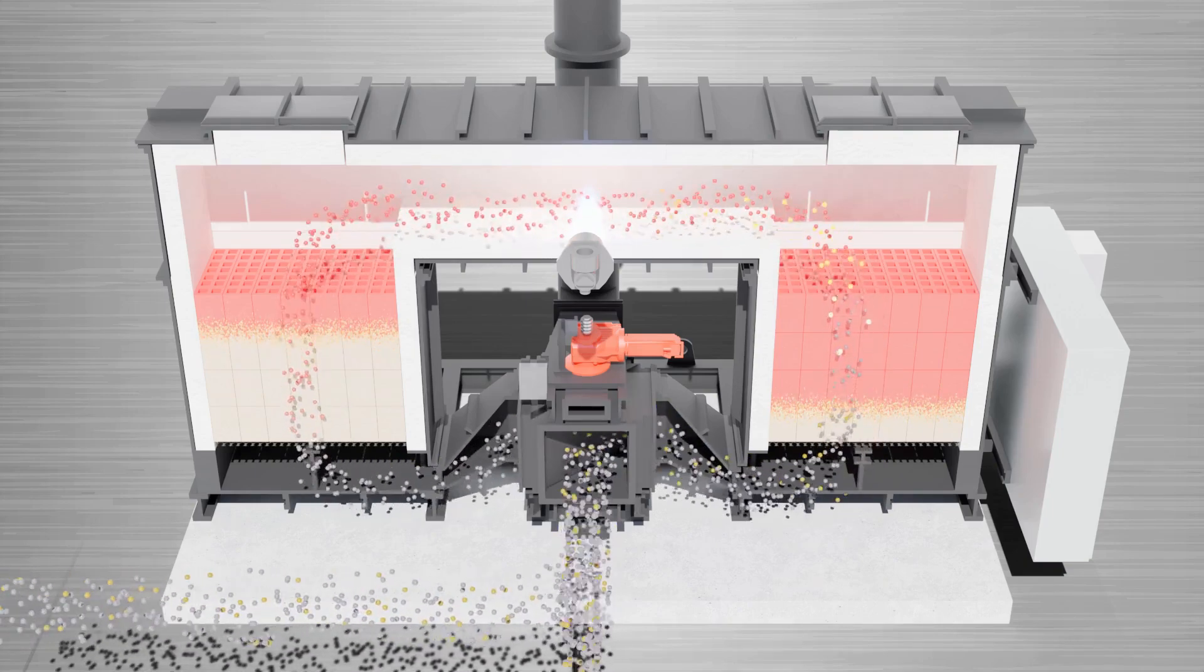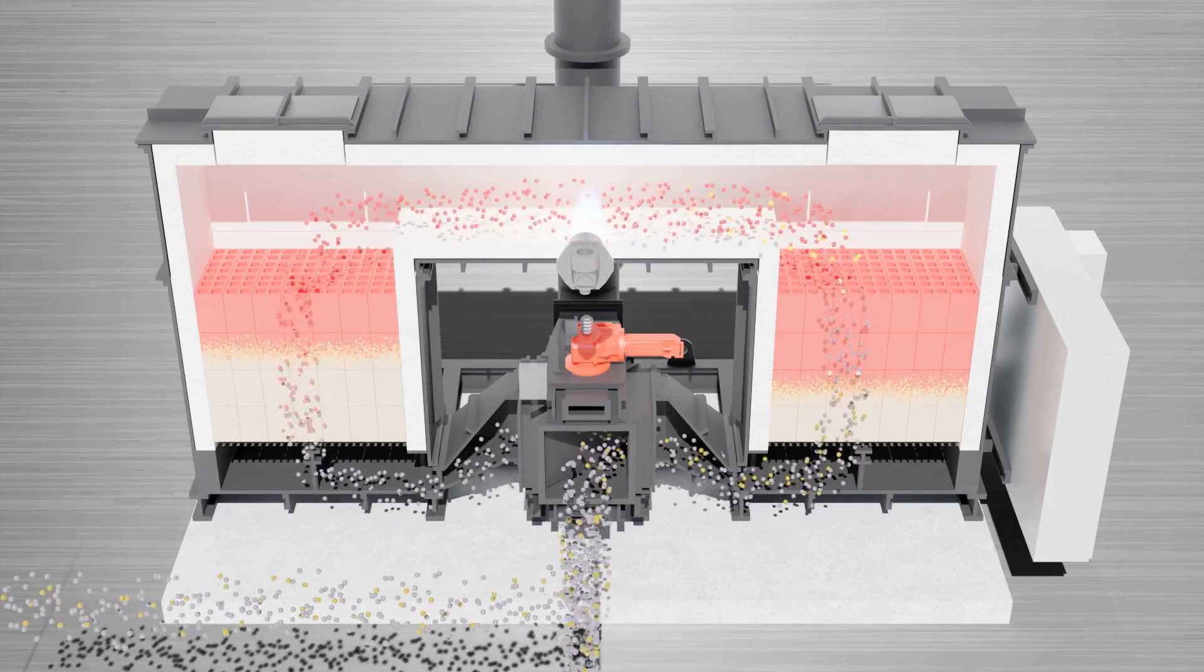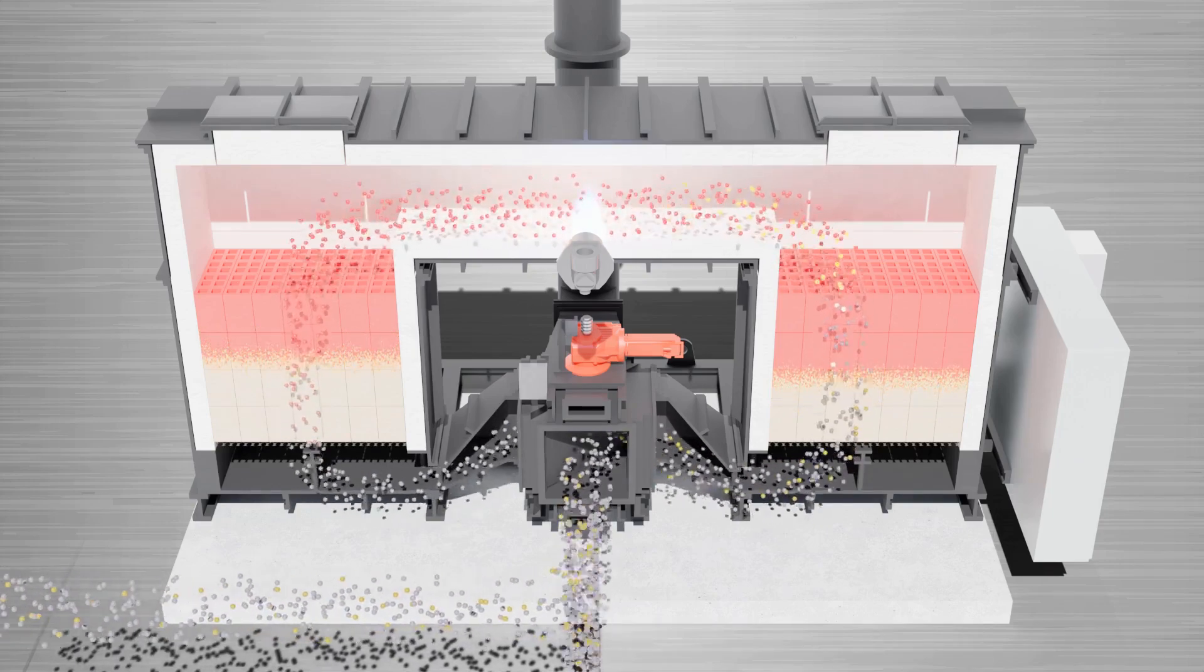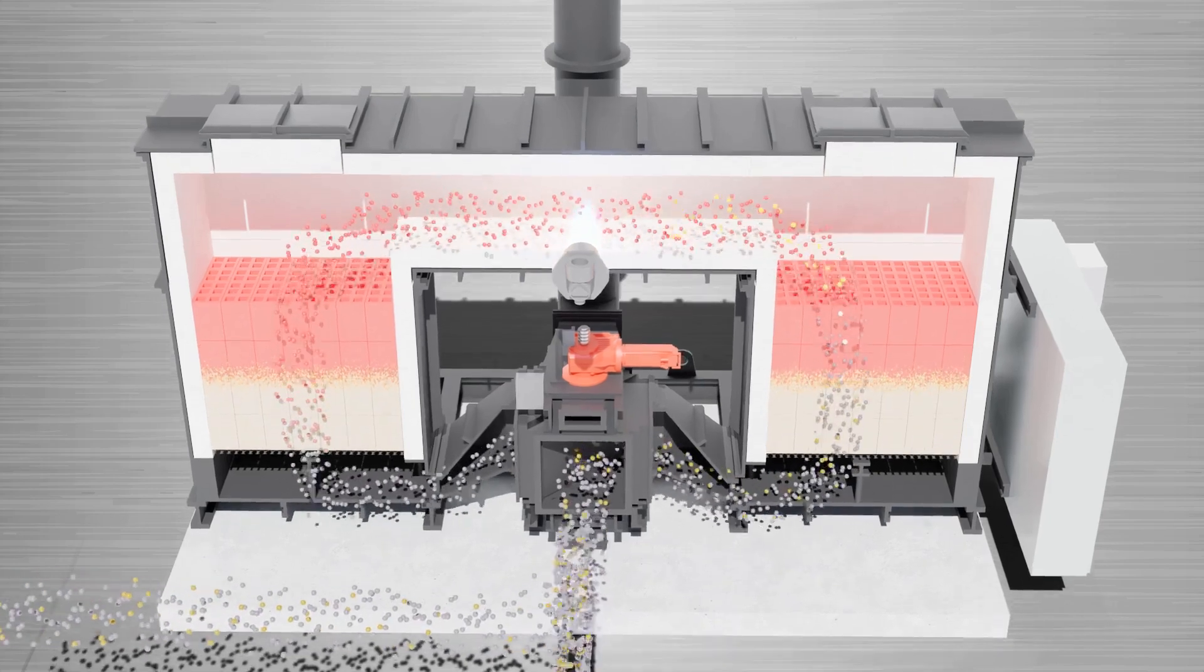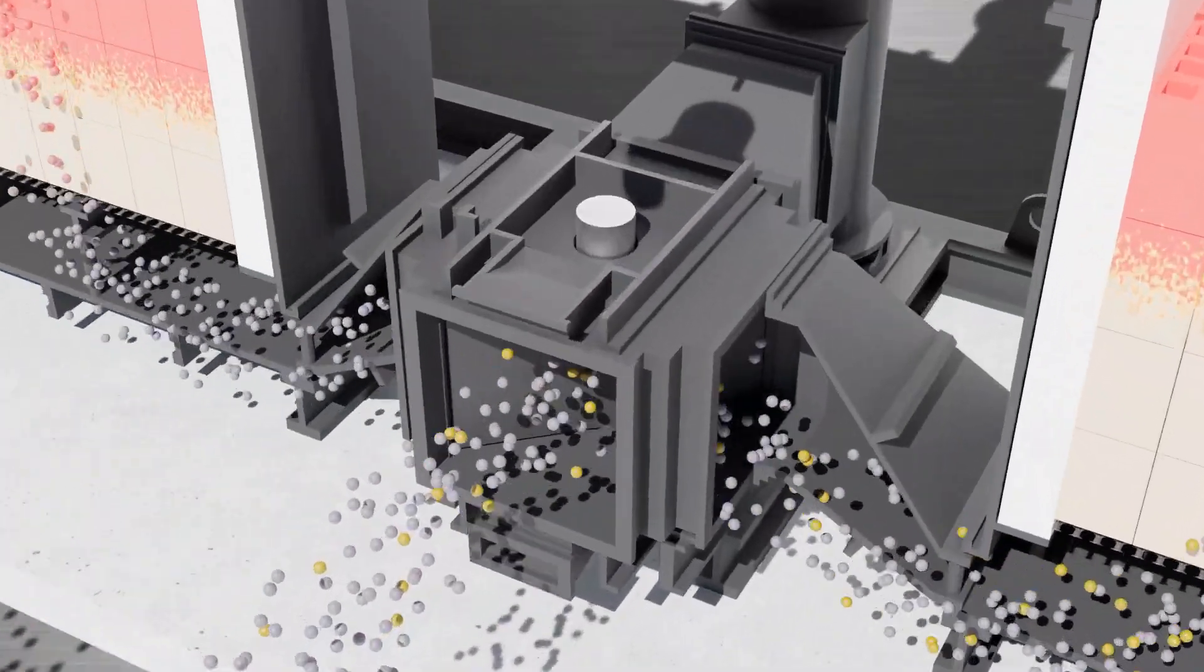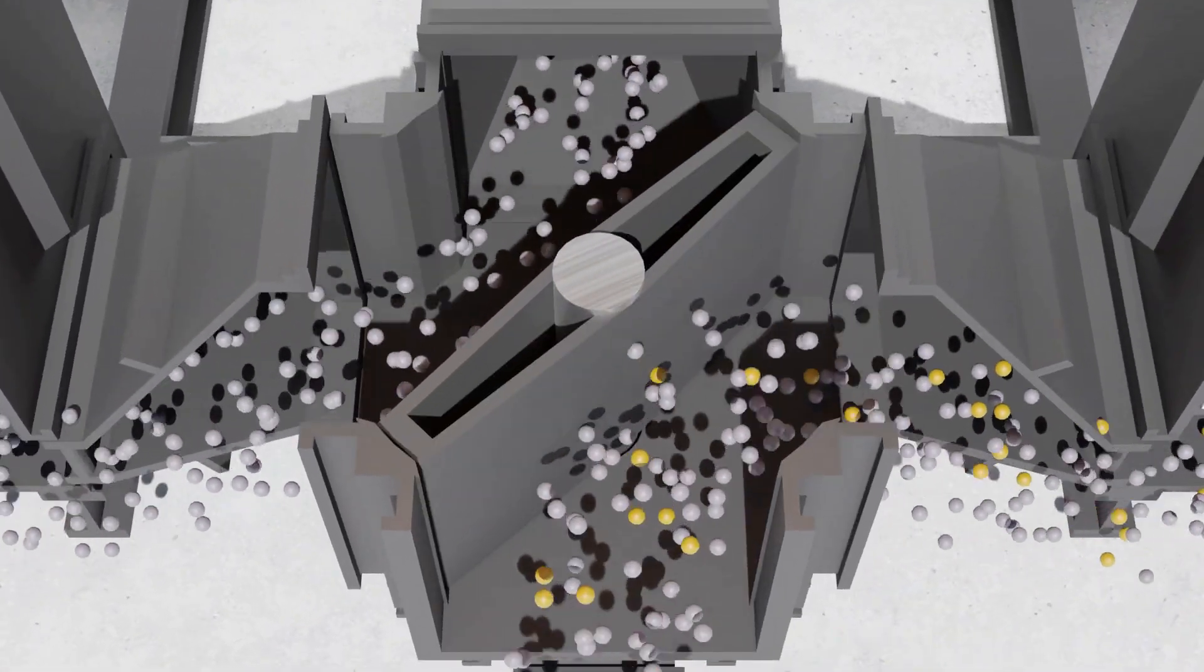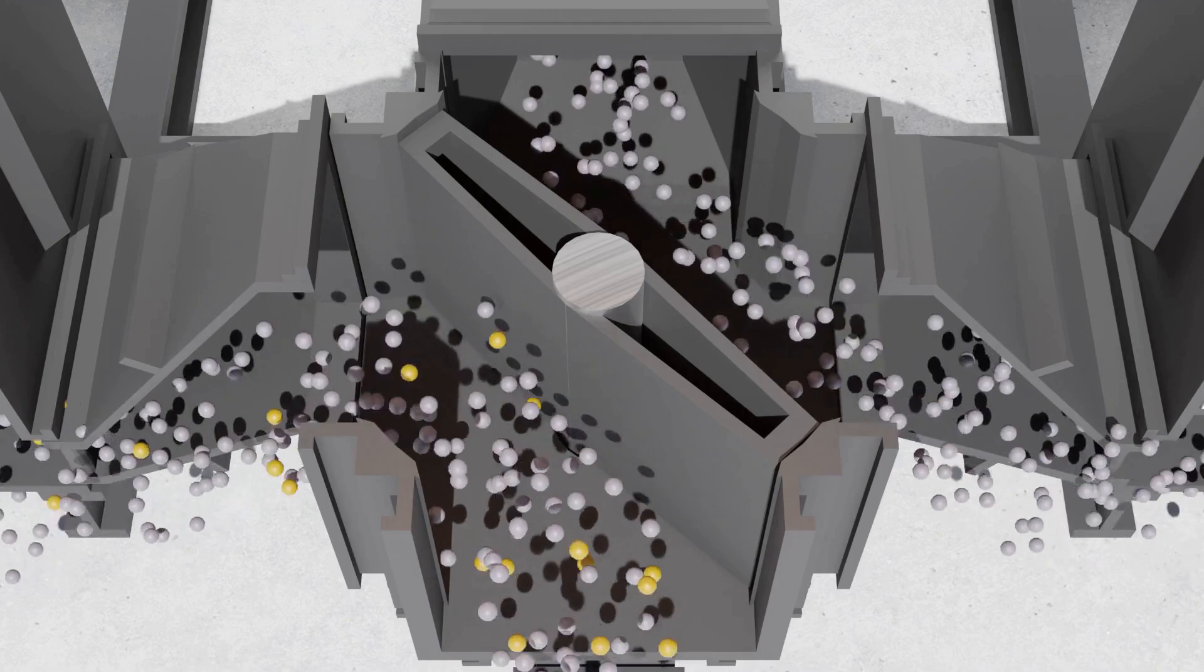The QS valve switches flow every two to five minutes in a continuous preheat and heat recovery cycle. This is how RTO systems achieve high destruction performance while greatly reducing fuel usage. In fact, some applications require zero fuel. In this case, the system is maintained solely by the heat release of the gas contaminants.